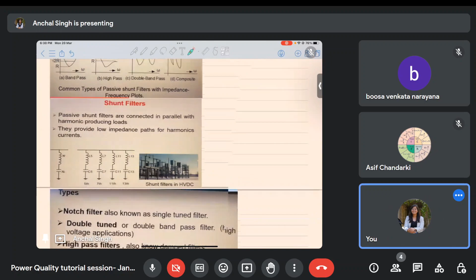If you want to design a shunt filter for fifth, seventh, 11th, and 13th harmonics, it would look something like this: each branch takes care of each harmonic, and for the rest of the harmonics, that branch just acts as a high impedance branch as if it is not existing.